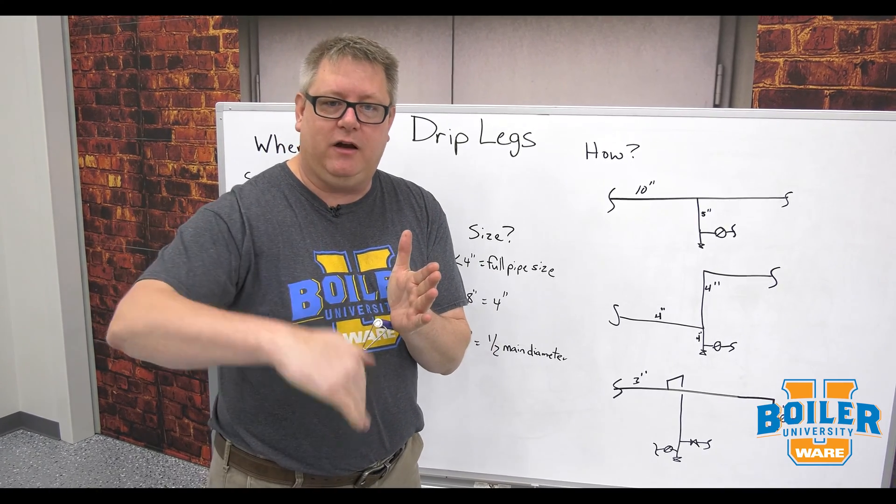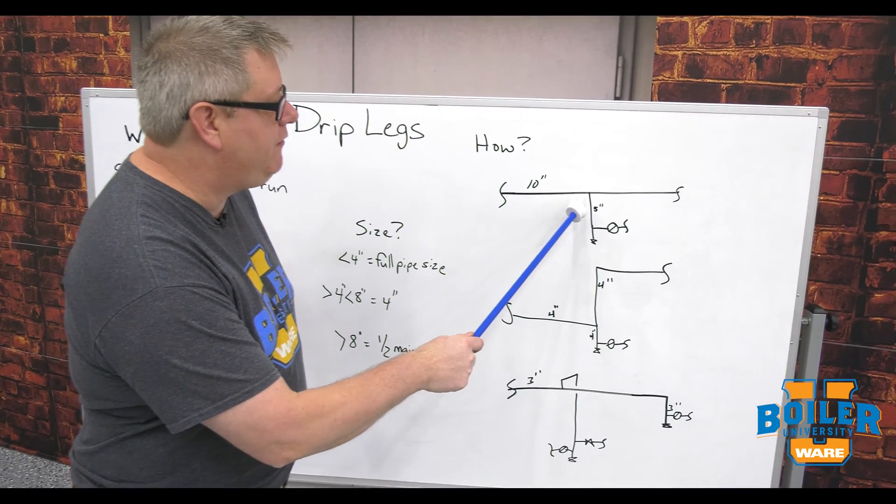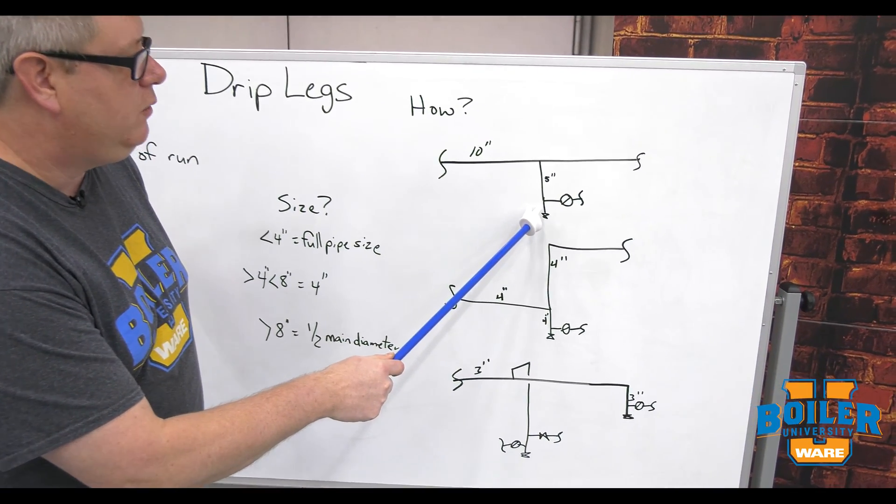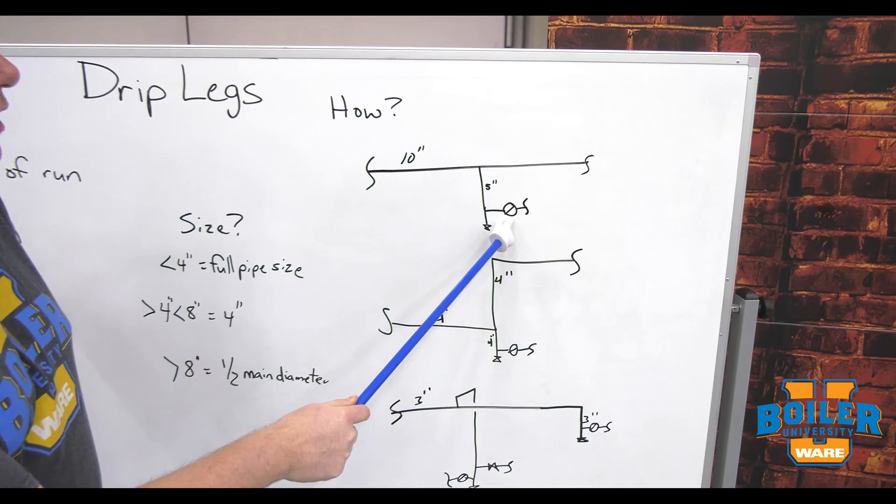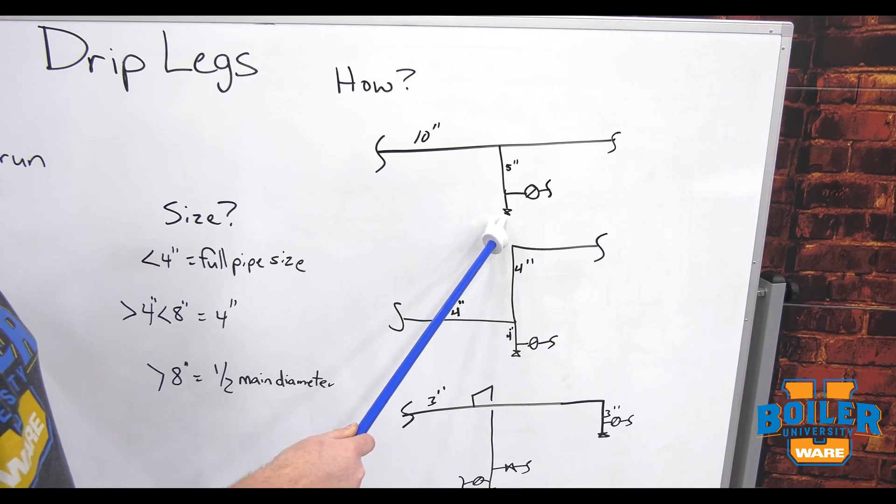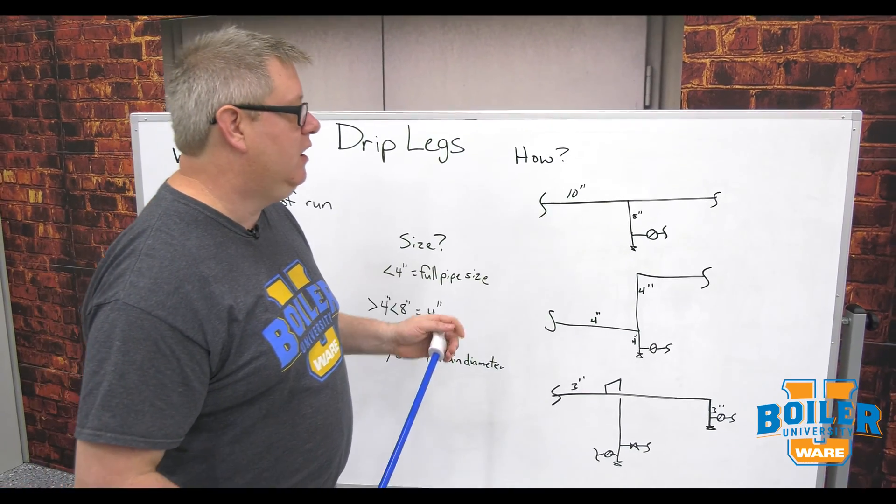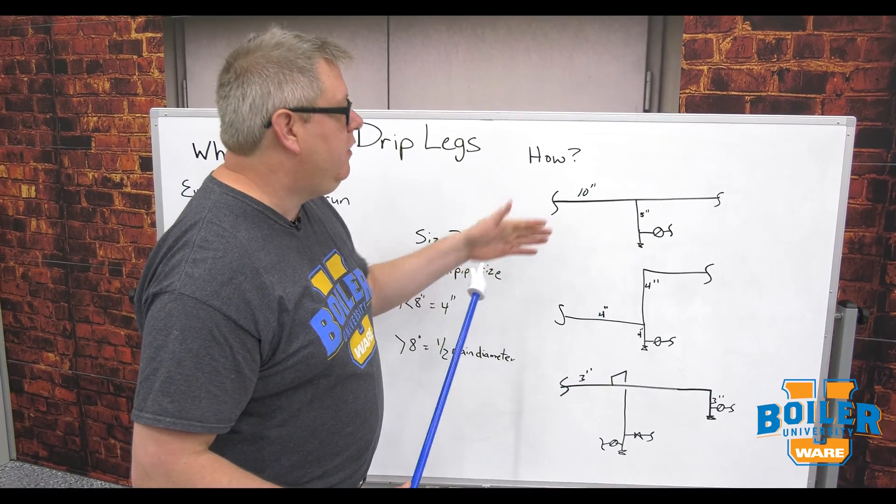In this case we would come directly off the bottom of the header. We would tee out the side with our trap, and we always want to put a drain on that as well for system startup. We can open that drain, clear condensate for troubleshooting, etc. There's some additional piping associated with the trap.